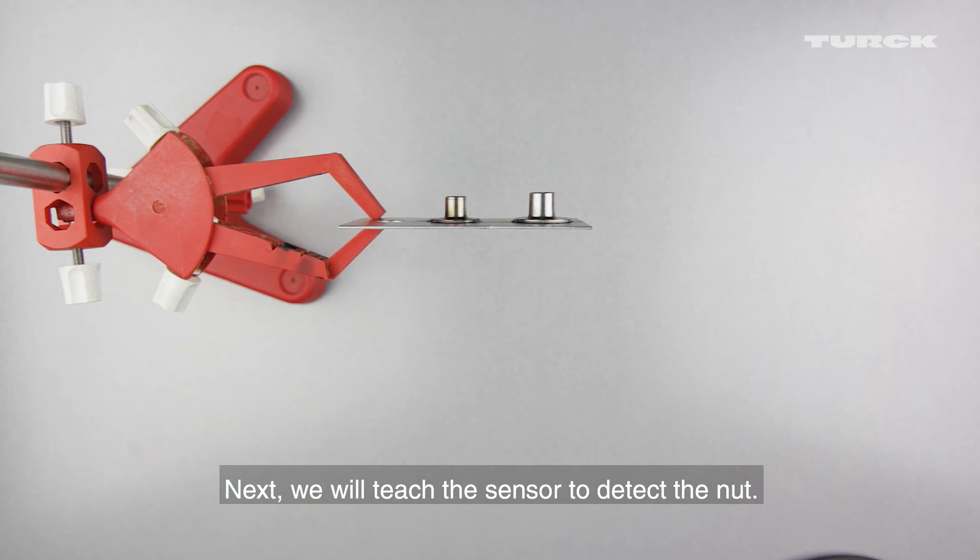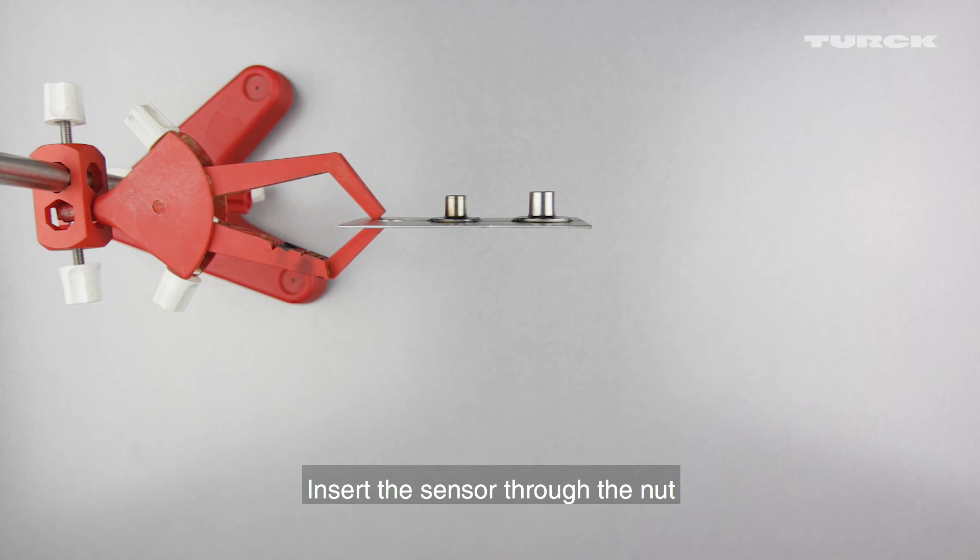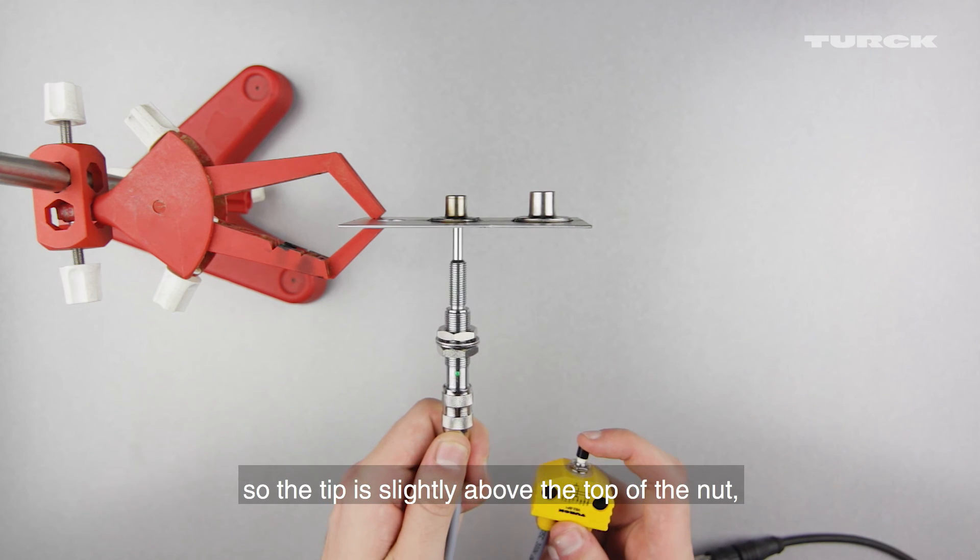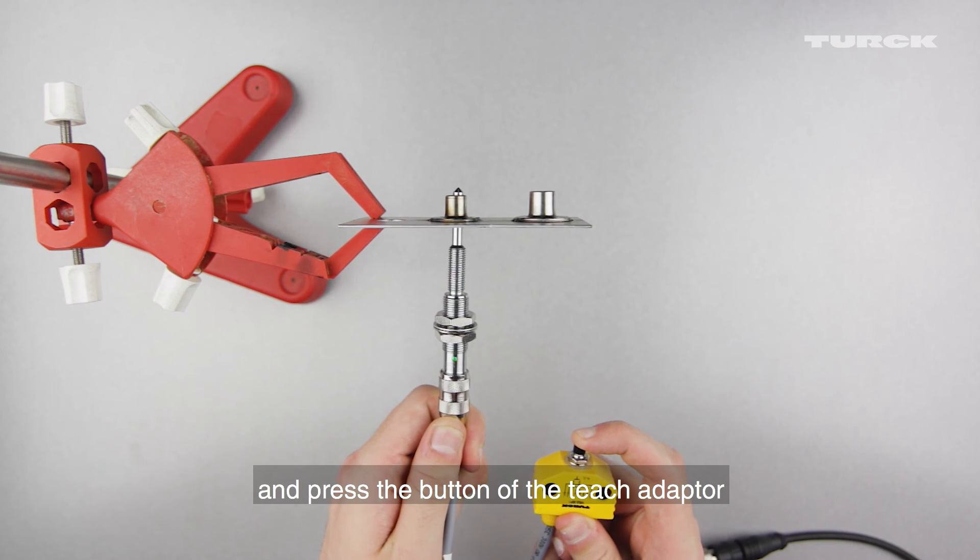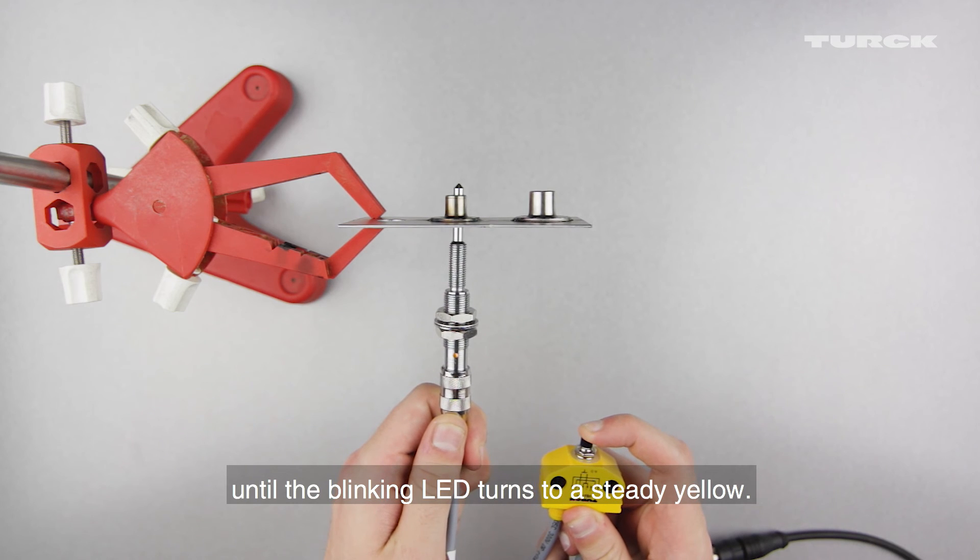Next we will teach the sensor to detect the nut. Place a nut on the sheet metal. Insert the sensor through the nut so the tip is slightly above the top of the nut and press the button of the teach adapter until the blinking LED turns to a steady yellow.